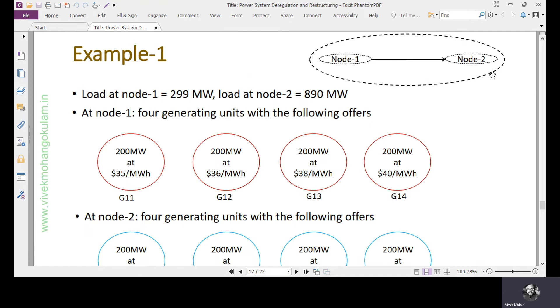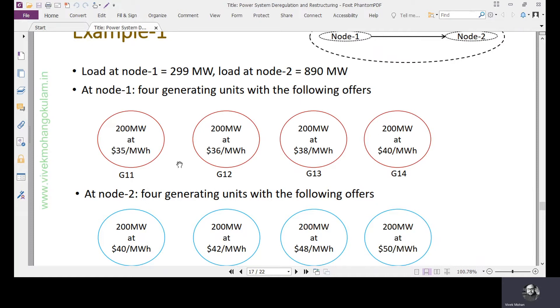We have two nodes — node one and node two — with two loads. Load one is connected to node one at 299 MW, and load two is connected to node two at 890 MW. Total system load is 1,189 MW. To feed this, we have 8 generators with offers at $35, $36, $38, $40, $40, $42, $48, and $50. The red generators are at node one and the blue generators are at node two. We start filling total load demand of 1,189 MW from the cheapest generator.